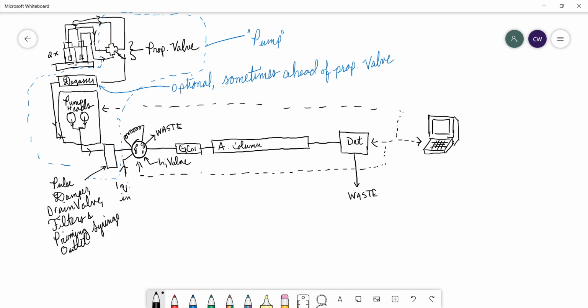And those are either under pressure and filtered, or they are degassed later on, and they feed into a proportioning valve. Okay, that proportioning valve will open for certain amounts of time to make sure that the mobile phase concentration settings that you have from the computer, which is over here, are in effect by the time the mobile phase reaches the pump head. Okay, so say you have solvent A at 50%, solvent B at 50%, the proportioning valve will have solvent A open for 50% of the time, solvent B open for 50% of the time, and it'll just switch back and forth between the two.